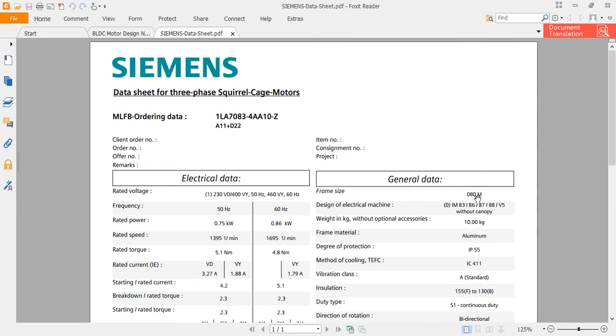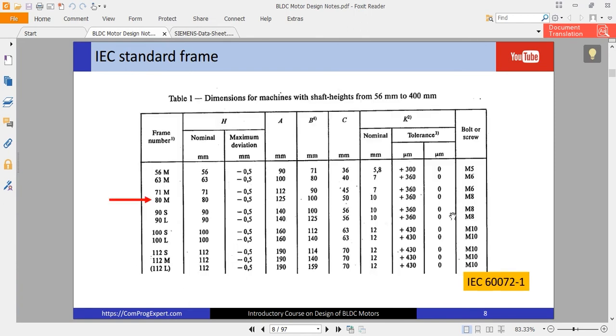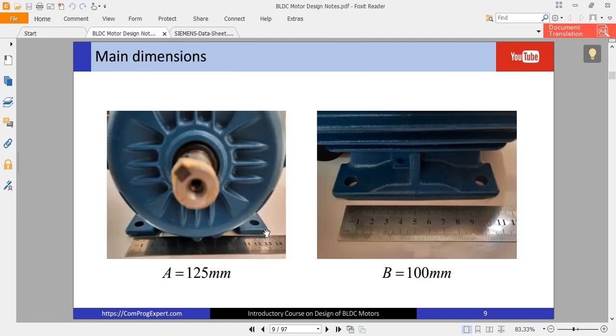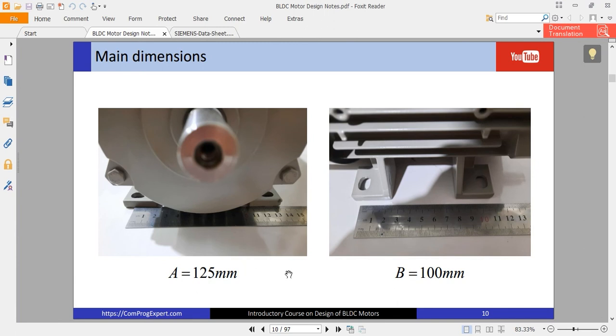The frame designation is 80M. The value of H, as you can see in the table known as frame number 80M, gives A equal to 125 mm and B equal to 100 mm, along with other dimensions. You can see these dimensions: A is 125 mm and B is the axial distance between the centers of the two holes on the foot. This is the WEG motor and this is the Siemens motor.